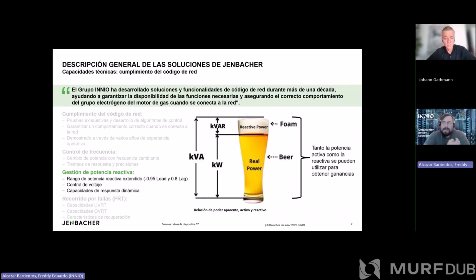Why is it important? To support the electrical system, mainly talking about the voltage aspect. Thanks to our standard design, from minus 0.95 underexcited to plus 0.8 overexcited for all generators, we can greatly help absorb and produce reactive power, positively impacting voltage control by raising or lowering it. We also have a fairly quick dynamic response capability, and all of this helps with the stability of the system.